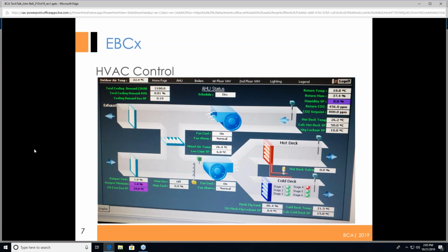Okay, here's a screenshot of an air handling unit. This is of an older setup, an older hot and cold deck arrangement. But we can notice immediately, just by going through our typical process, where we do the review of the site, the installation review, look at the equipment, monitor or at least visually investigate how things are operating, and then of course go through the automation system if it has one, right? We can see things aren't quite lining up.